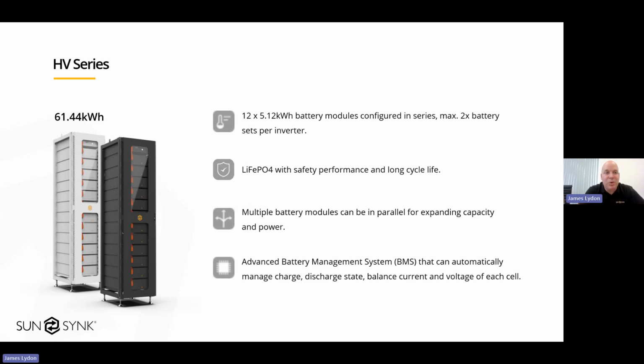The batteries that they will work with are high voltage batteries. You can see in the images here there are 2 stacks. Each stack is 61.4 kilowatt hours of storage. There are actually 12 5.12 kilowatt hour low voltage batteries in that stack, but because they're connected in series rather than parallel, once we're at the top and connecting to the BMU, that's when we're at 600 plus volts. Again, LiFePO4, so lithium iron phosphates are really safe.